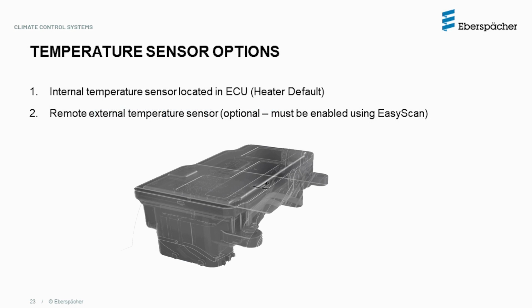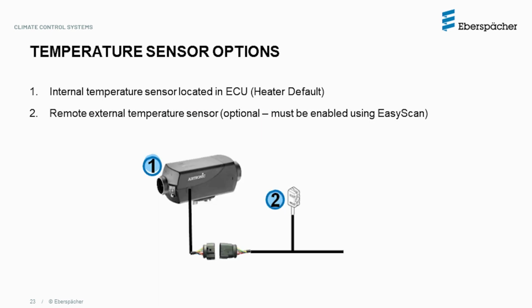The Airtronic 2 heater has a built-in sensor located in the ECU, and it is the default ambient air sensor for operational control. However, an external remote sensor can be connected to the heater harness and used for operational control. But this is only possible when the heater is operated using a CAN-based controller like the Easy Start Pro. The external sensor is not automatically set as a default ambient air sensor. The installer will have to manually set it with the Easy Scan diagnostic tool.